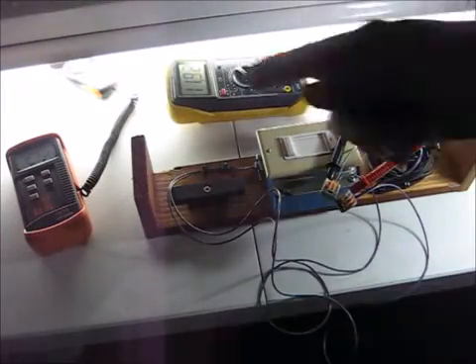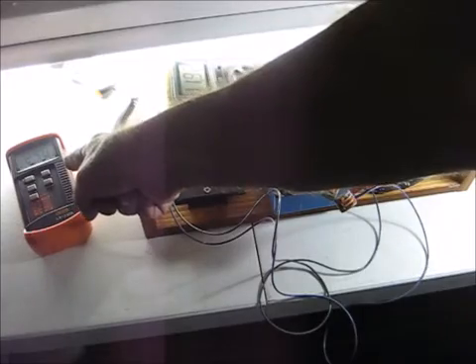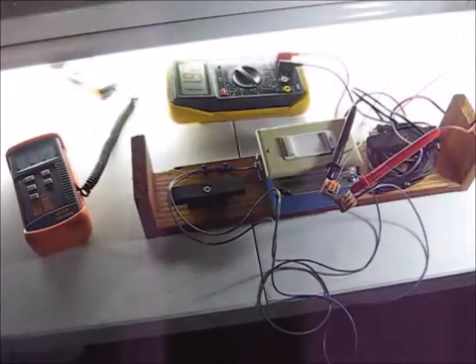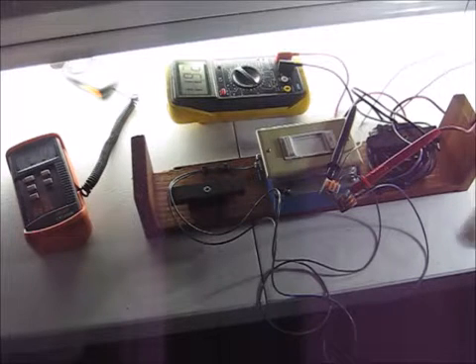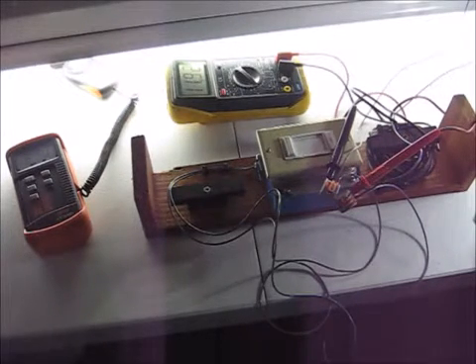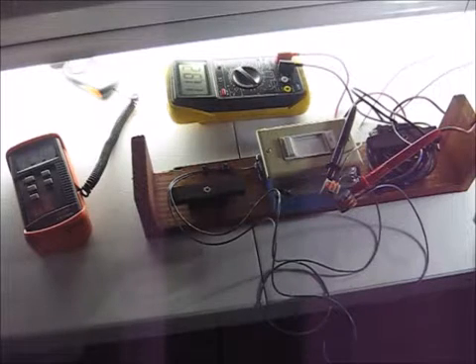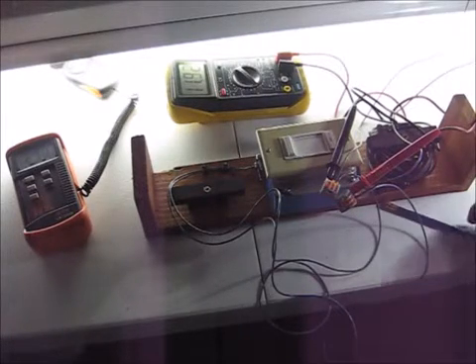Now we're going to look at our control voltage with the dimmer all the way up. I see 1.92 and I didn't see my light meter twitch. So we're going to start at 240 and we're going to bring down the control voltage to try and find where our first top end dimming occurs. So let's start bringing it down, feeling it out.